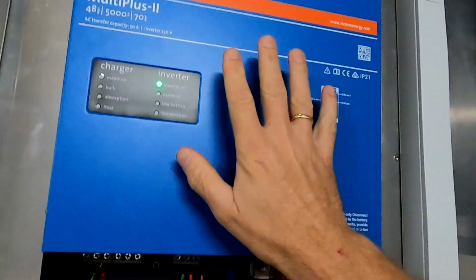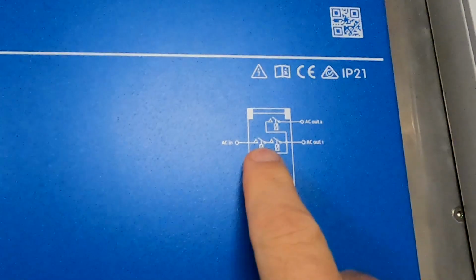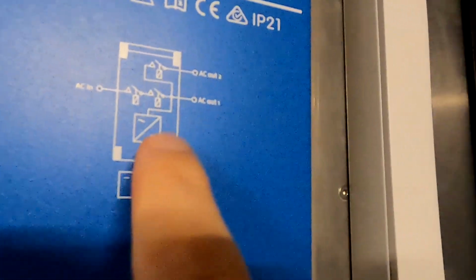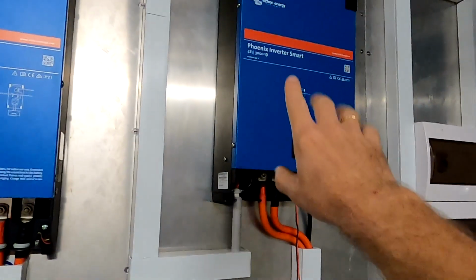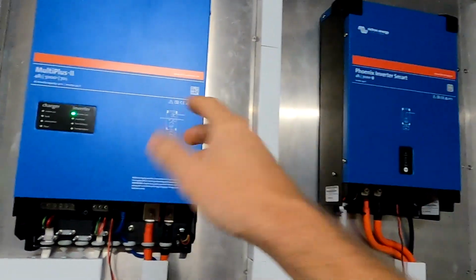Now I understand why it makes those loud clicking sounds inside - it's the two transfer switches. One disconnects our generator, and then the other turns on the MEN link relay, the bonding between ground and neutral. That's what we're hearing. I thought it sounded like the relay wasn't switching correctly and needed two attempts, but no - there are two different relays: one disconnects AC, the other reconnects the ground and neutral bonding. I remember reading this in the manual. It does the same thing before connecting to the generator: turns off the MEN link, then connects to the generator. In our case this unit already has an MEN link built in, so it turns off when needed, and when running standalone like now, it turns the MEN link back on. This is exactly what it's supposed to do.